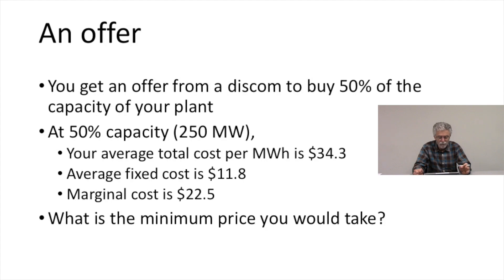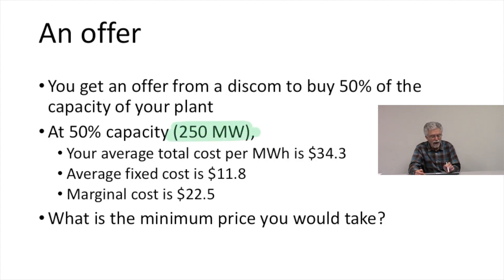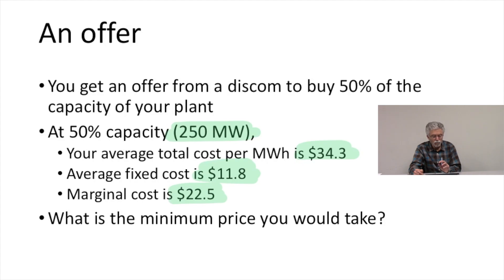Let's suppose you get an offer from a DISCOM to buy 50% of the capacity of your plant. At 50% capacity that's 250 megawatts. At 250 megawatts, your average total cost per megawatt hour is $34.30, the average fixed cost is $11.80, and the marginal cost is $22.50. So the question is: what is the minimum price you would take to supply this 50% power from this plant?